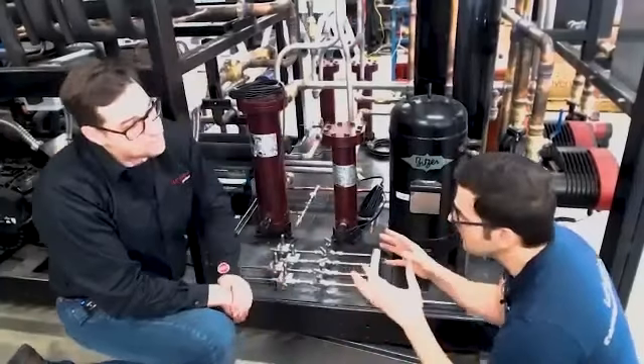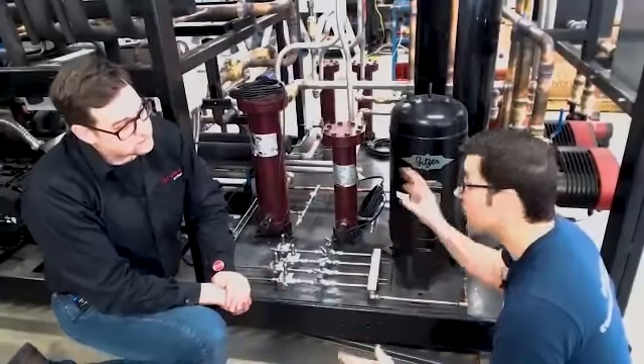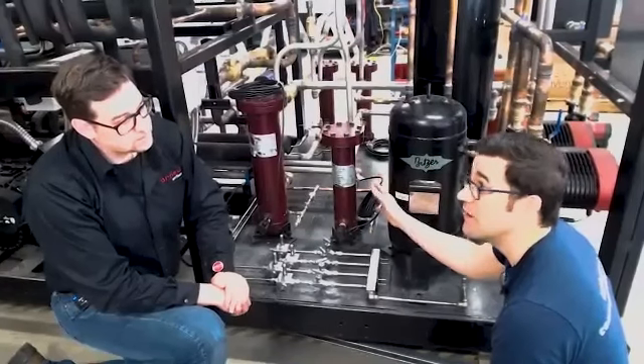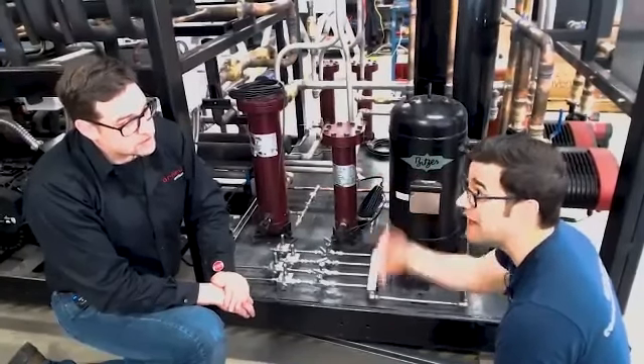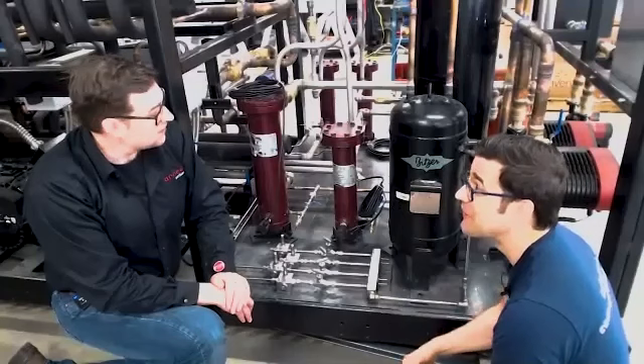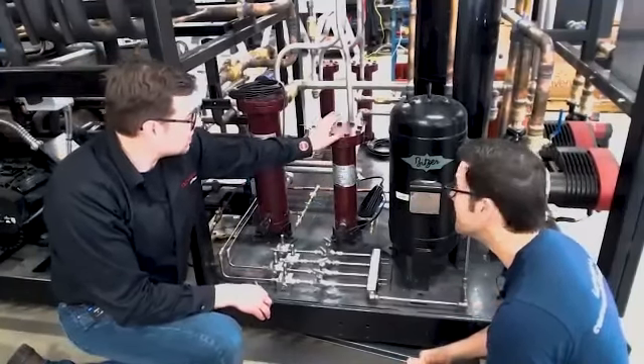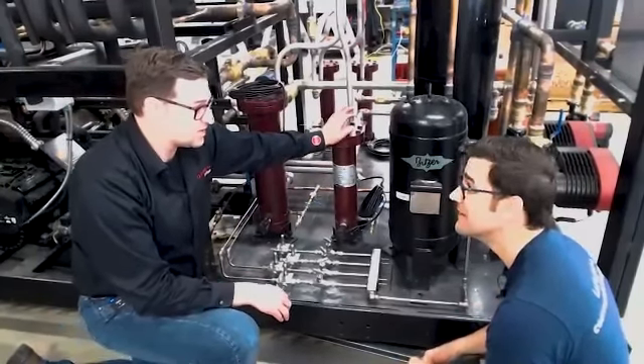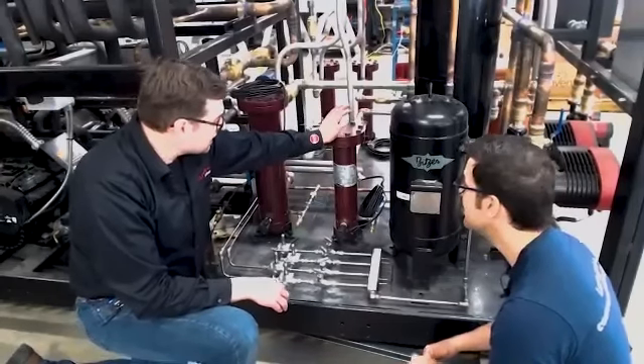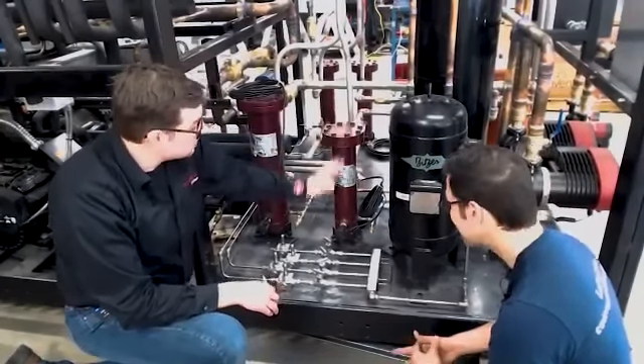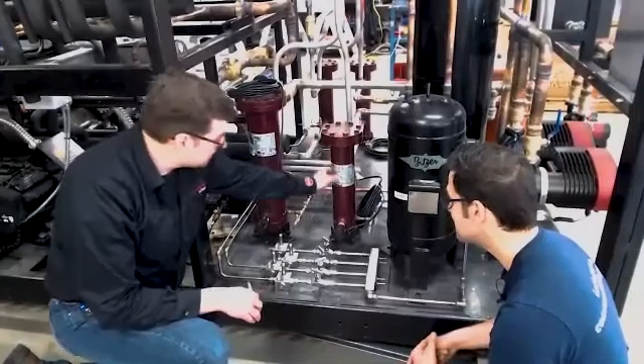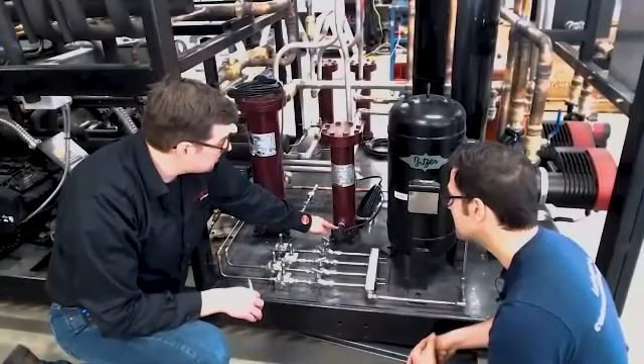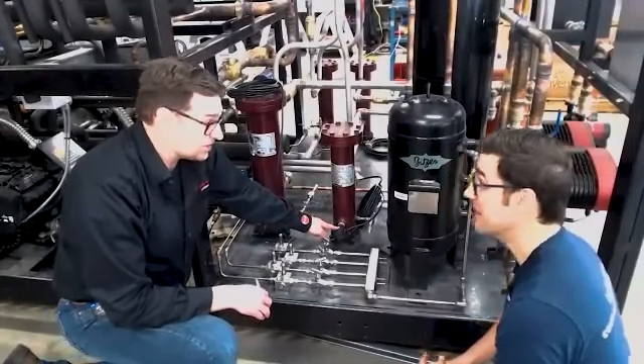I've seen that time and time again, where there's a blown filter in there for months and people don't recognize it, they just keep adding oil. Filters are going to blow around 60, 65 pound pressure differential, and by all means we shouldn't be getting there. A blown filter isn't only problematic for the filter debris inside, but we're likely going to mess up our oil feed in that situation.